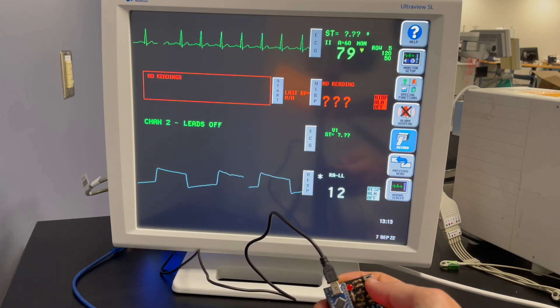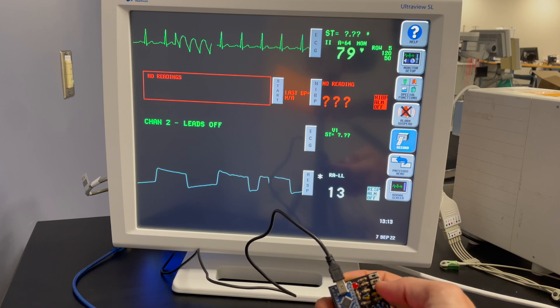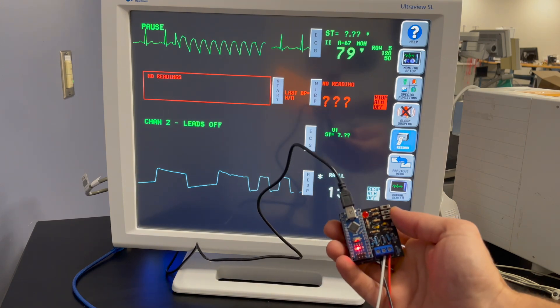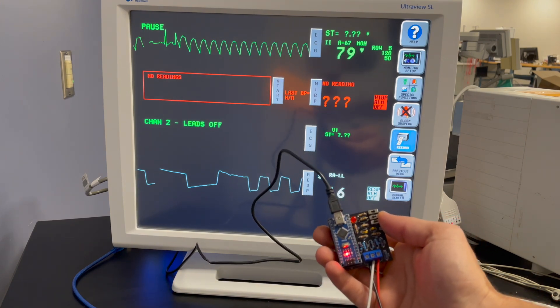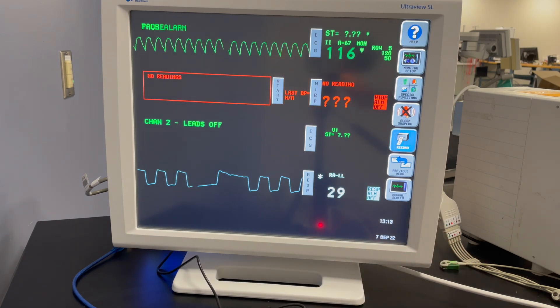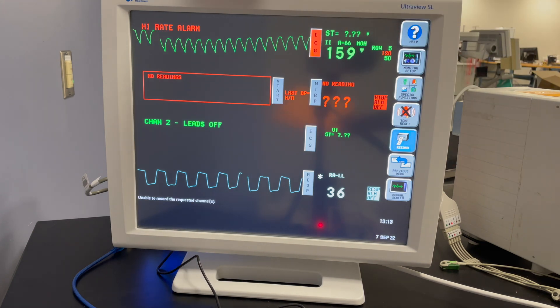Now in this case we're going to just flip the bottom two toggle switches to the left in order to simulate tachycardia. And you can even see that the tachycardia alarm shows up.